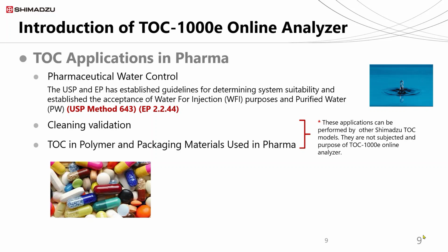You have to perform the system suitability test according to USP 643 and EP 2.2.44 for WFI and pure water. Unfortunately, you cannot perform cleaning validation by the online TOC-1000e model. You have to use other Shimadzu TOC models, not online, and accessories.